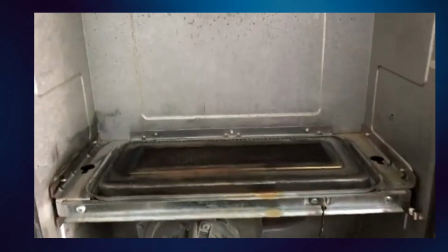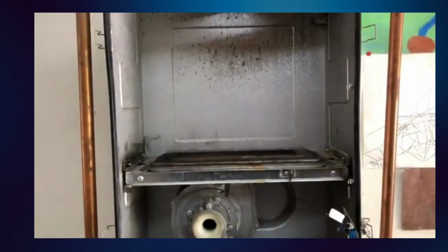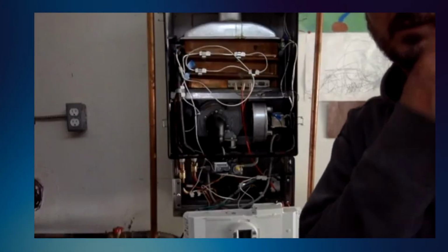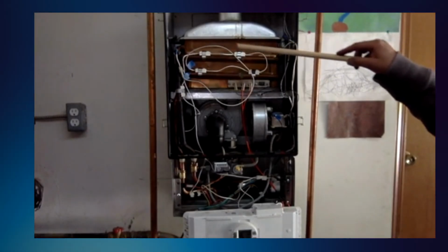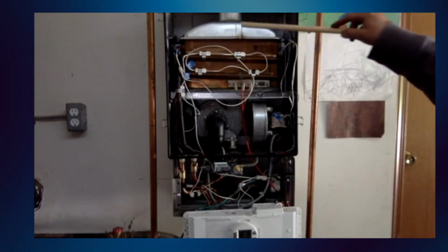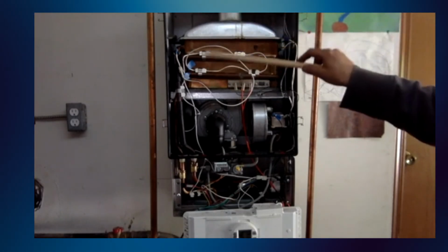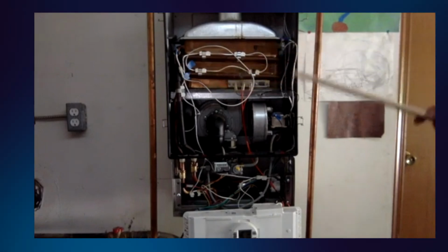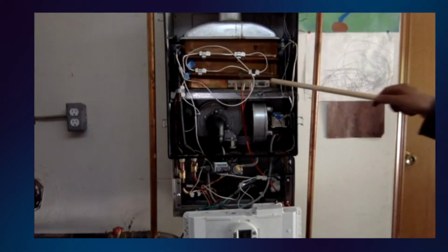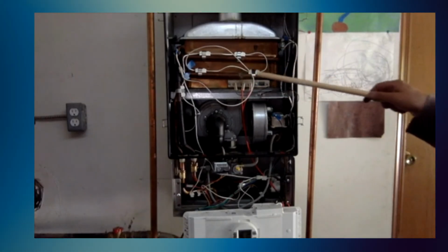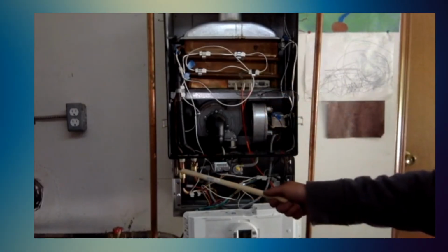The pipe may need better insulation, a different route, or correct fall to the drain. The fifth cause is a blocked flue outlet or poor airflow. The boiler needs correct air intake and exhaust. If the flue terminal outside is blocked by leaves, snow, ice, debris, nesting material, or an obstruction, combustion can fail. You can visually check the outside flue terminal from a safe position, but do not dismantle it and do not insert objects into it.